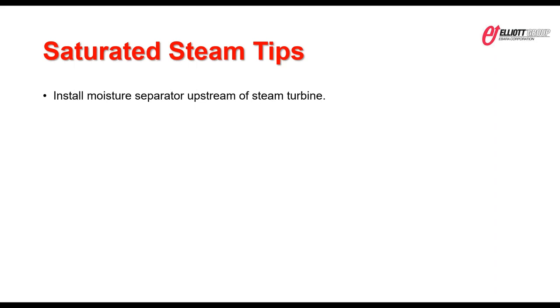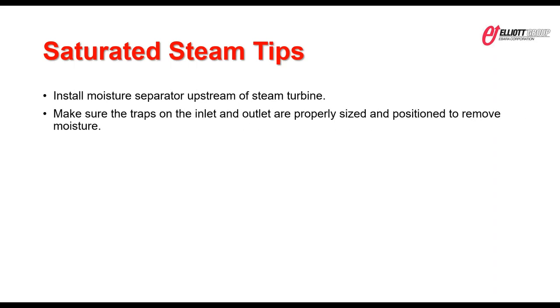That sounds odd, but when steam is dry, you can still be at that saturation point, and the steam is at least dry coming into the turbine, protecting the most critical components, the inlet valve and first stage nozzle ring. So it really extends the life of the equipment. The biggest helper, and certainly our number one recommendation, would be to install a moisture separator upstream of the turbine. It's something we can provide in our scope of supply, as a loose supply item, but that's probably the number one item that would really help reduce any moisture.